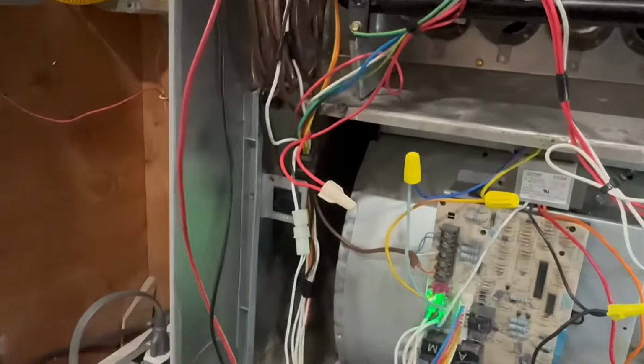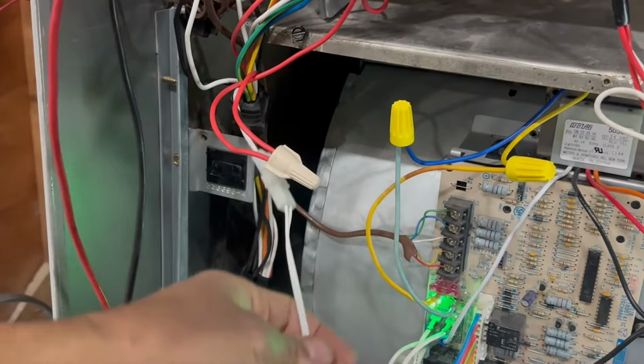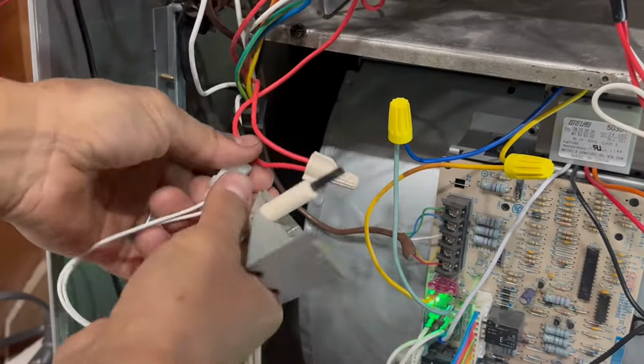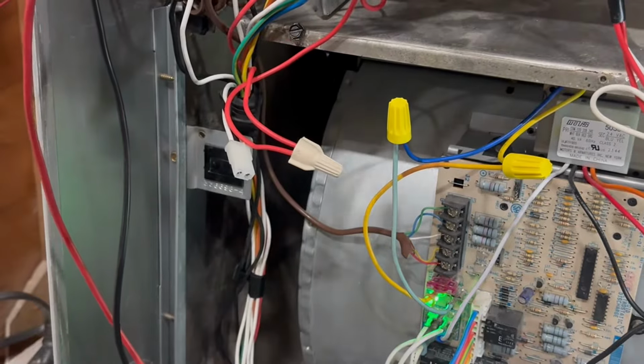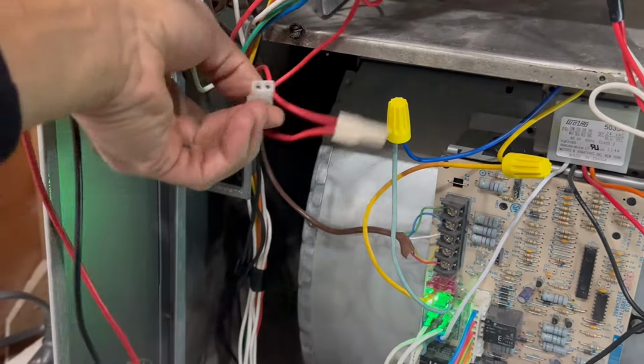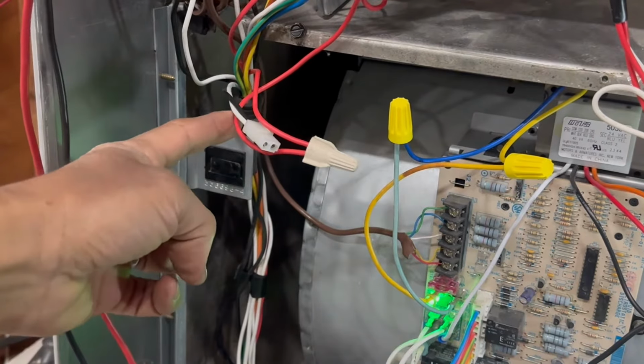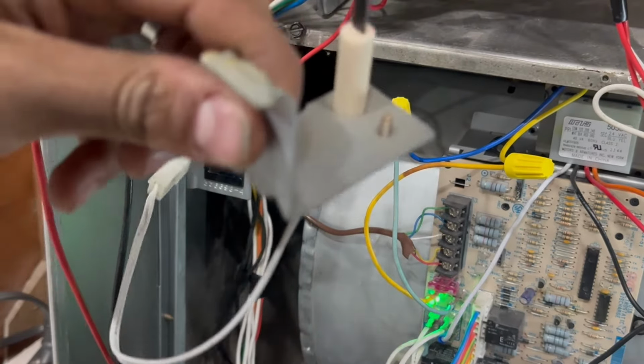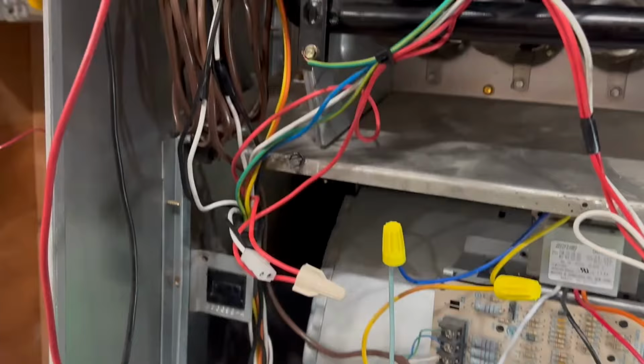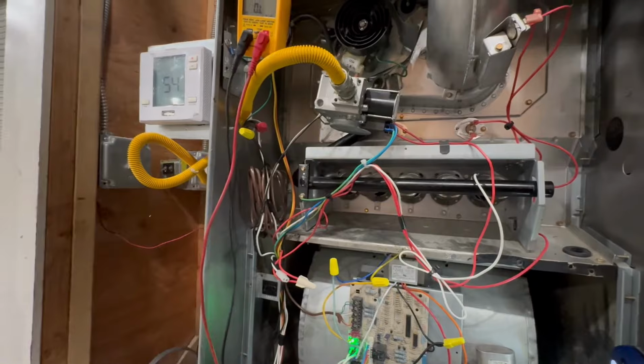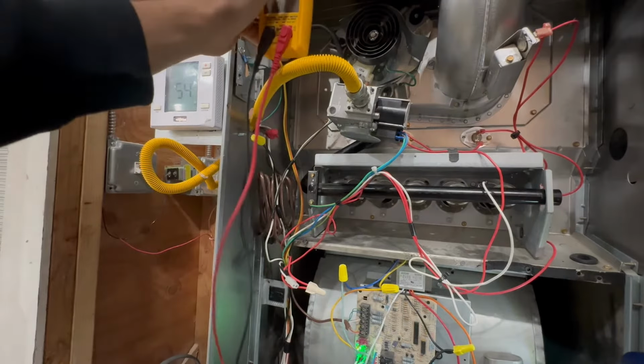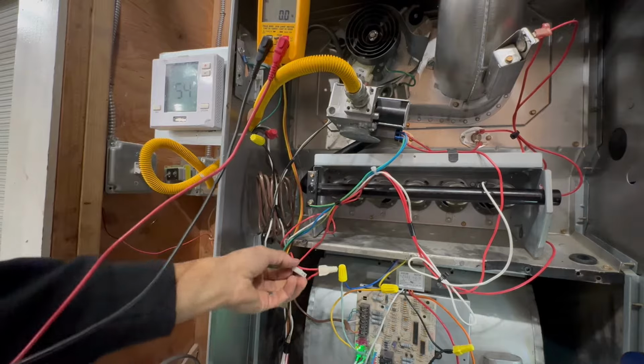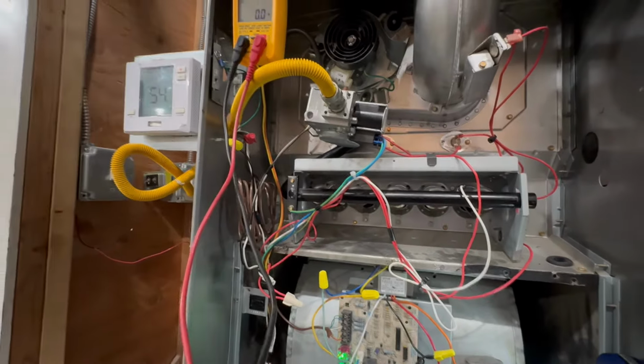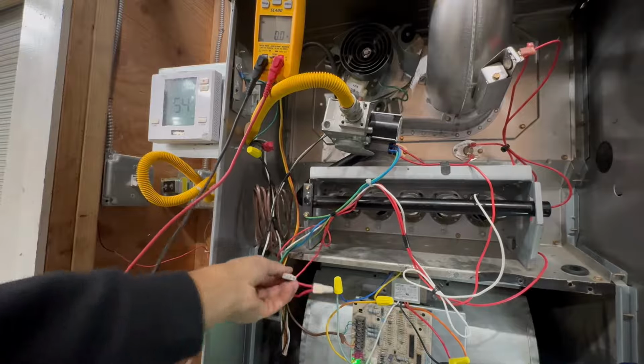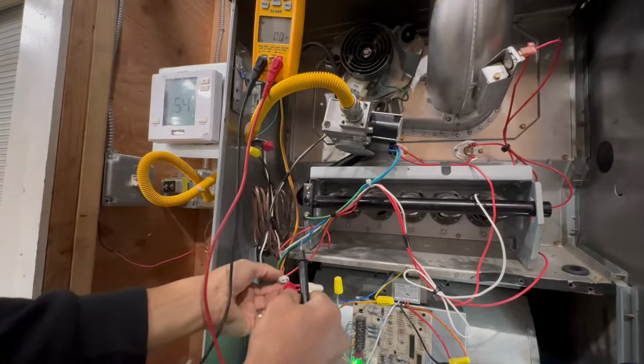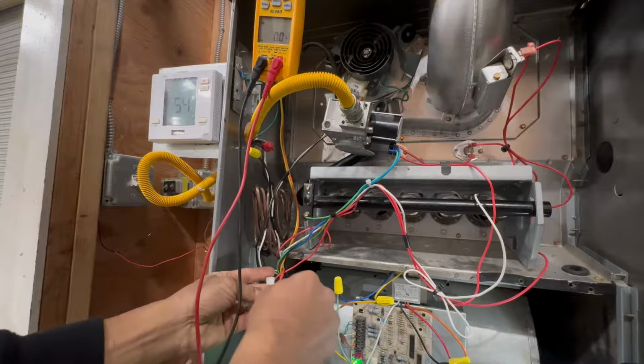So right here with this hot surface igniter, you see this one here. So I have the hot surface igniter. I'm going to pull this out. Right, I pulled it out. Okay, and I'm going to check now for voltage right there. This is what sends 120 volts to my hot surface igniter. So you'll see that it does send 120 volts. So let's get that meter up right there. Let's put it on volts, right? We've got to put it on volts. And let me see if you're able to see the meter. There we go. And I have my plug right here. So I'm going to go ahead and connect it first, right? And then let's go ahead.